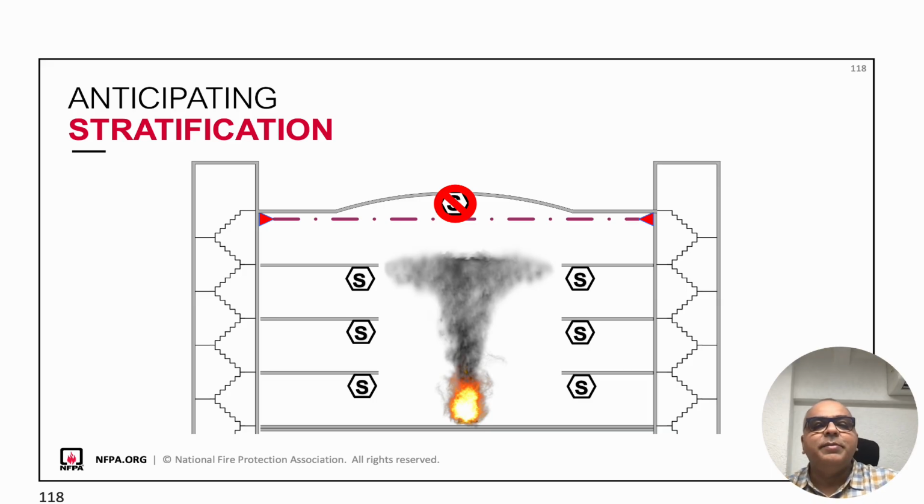What's happening here in this image? A fire at the ground level produces hot smoke. Smoke rises initially due to buoyancy and heat. At a certain height, it cools and stops rising. The smoke then spreads horizontally, creating a stratified layer. A dashed purple line represents the stratification level.